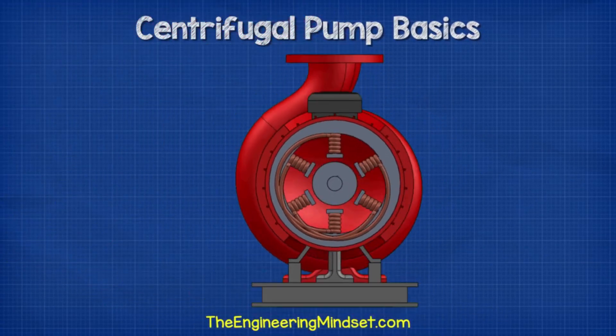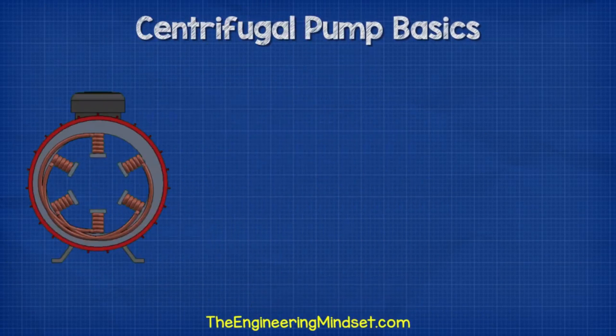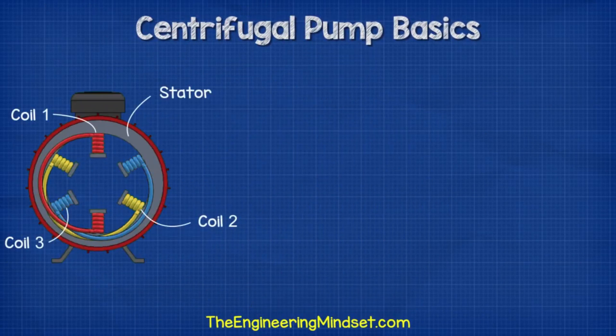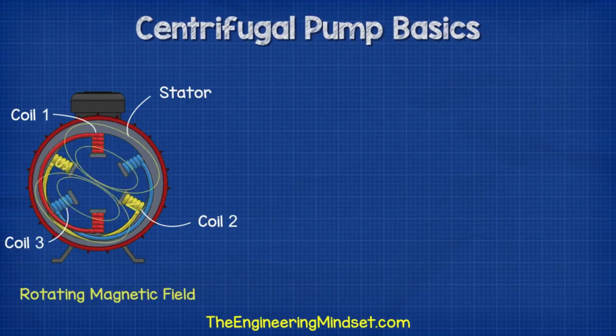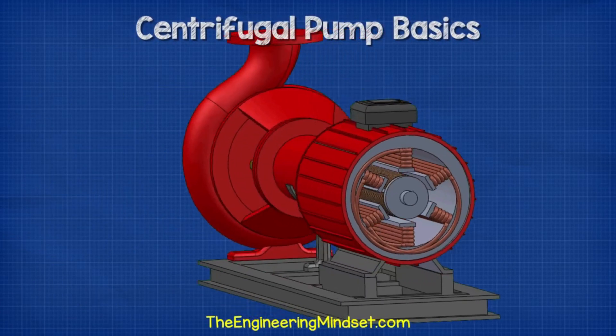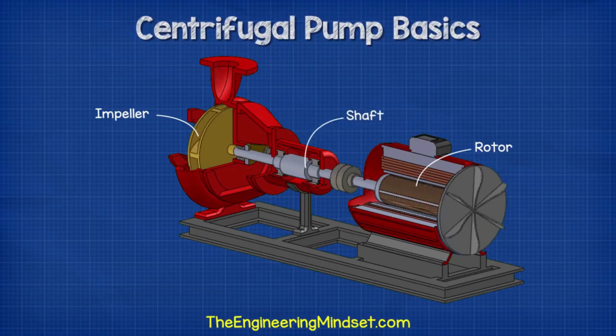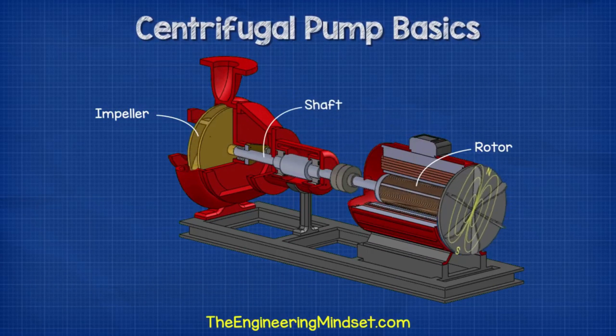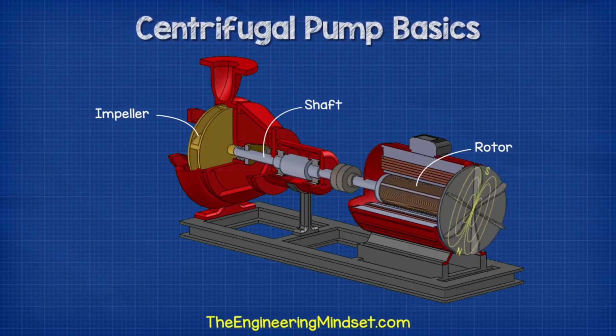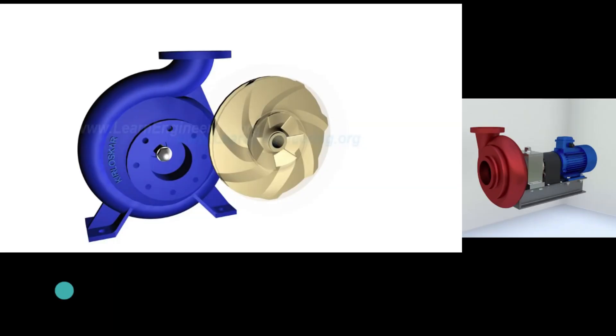We will look at the three-phase motor as it is the most common. Inside the three-phase induction motor, three separated coils produce a rotating magnetic field. The rotor is connected to the shaft, and when the rotor rotates so will the impeller. By creating a rotating magnetic field, we spin the rotor, which spins the shaft, which spins the impeller.